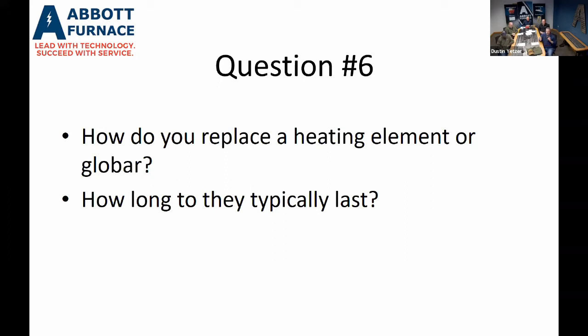A couple things, there's a distinction between the heating element and globar. Heating elements are usually what you see in the preheat. They're wire wound, usually on a support tube. Those are supplied in your preheats, and then your high heats are what they call glow bars, or silicon carbide heating elements, or heating tubes. That's called globar. Typically your glow bars are higher temperature. You won't see heating elements typically over 1800 degrees, because they start to sag too much above that temperature.